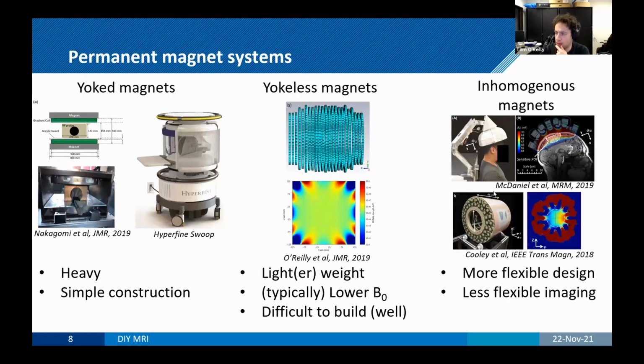And then you have the inhomogeneous magnets, which allow you to be very flexible in design. They're inhomogeneous, which means that they'll typically have the readout gradient that we use in MRI, the frequency encoding gradient, built into the system. Because you don't need a homogeneous magnet, you can be much more flexible in the design of your system, because, for instance, you only need magnets on one side. It does mean that you're much less flexible in imaging. So you're more flexible in design, but less flexible in applications. For the rest of the talk, I'm going to just focus on the yokeless magnet, just because that's what we have the most experience with.